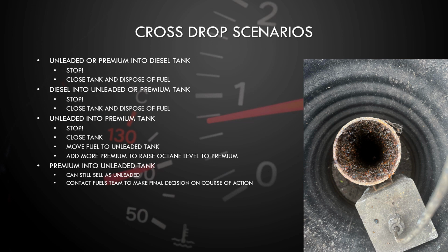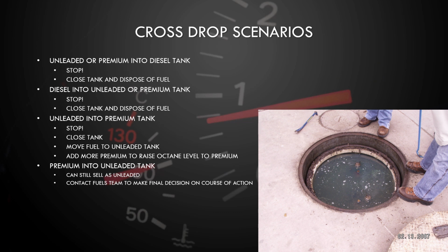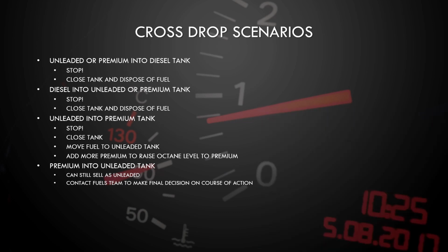In case someone drops unleaded or premium fuel into your diesel tank, stop selling fuel from that tank immediately. Close the tank and work with your HQ fuels team to get rid of the fuel. Diesel on unleaded or premium, that's still the same scenario. Stop, close tank, get hold of HQ fuels.